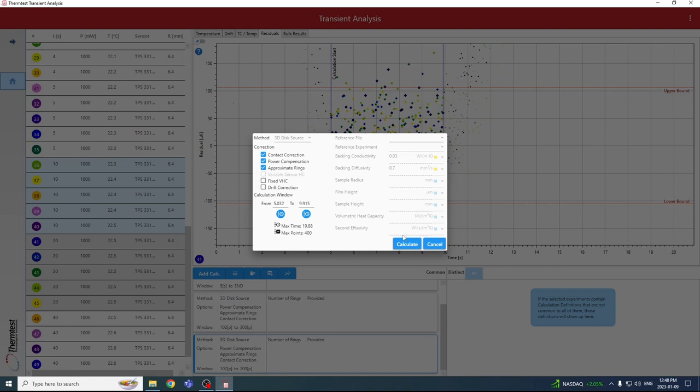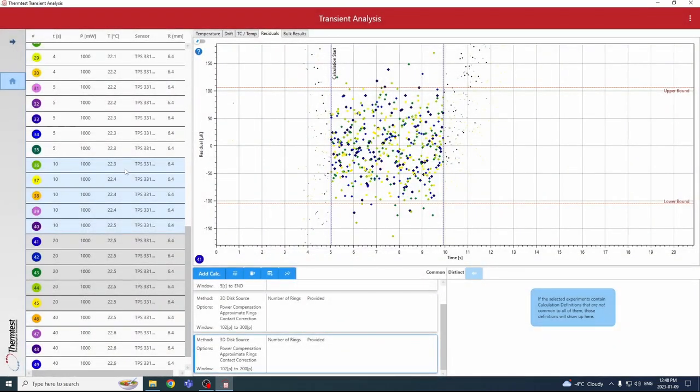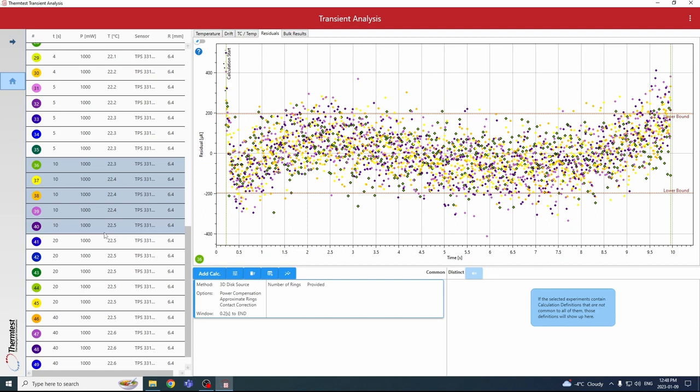So with that, this data is okay, and it's fine to use data that you removed points from, especially if that's all you have and you've made measurements of longer test times. But you can also use longer test times to identify what your ideal test time is. So we've identified from this that 10 seconds is our ideal time for the available dimensions on this sample. So why not measure for the whole 10 seconds so that we can maximize the number of points used in our calculation.